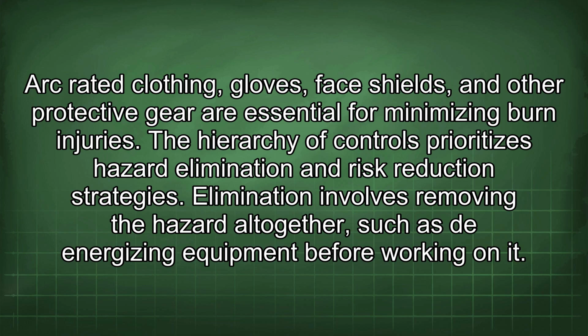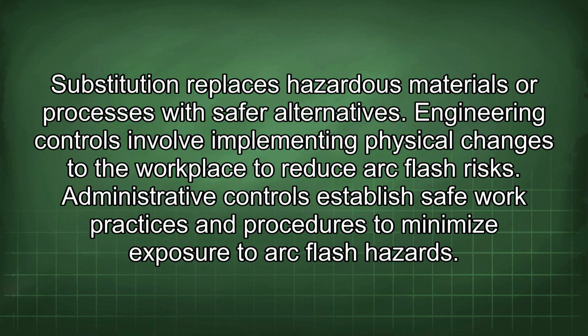The hierarchy of controls prioritizes hazard elimination and risk reduction strategies. Elimination involves removing the hazard altogether, such as de-energizing equipment before working on it. Substitution replaces hazardous materials or processes with safer alternatives. Engineering controls involve implementing physical changes to the workplace to reduce arc flash risks.